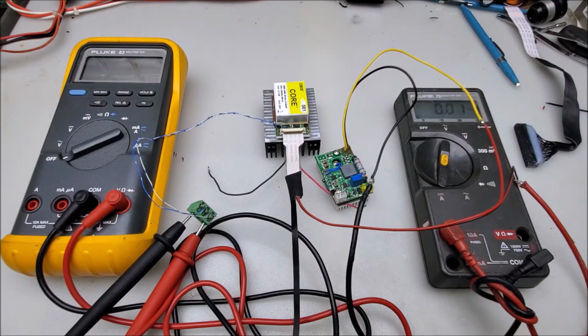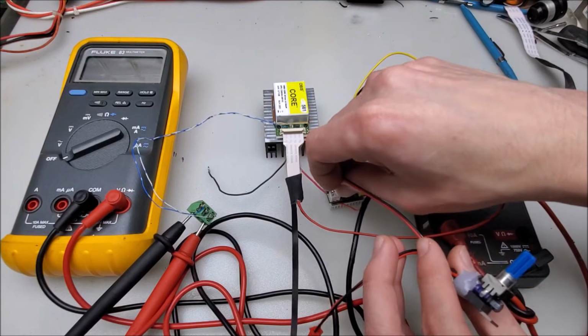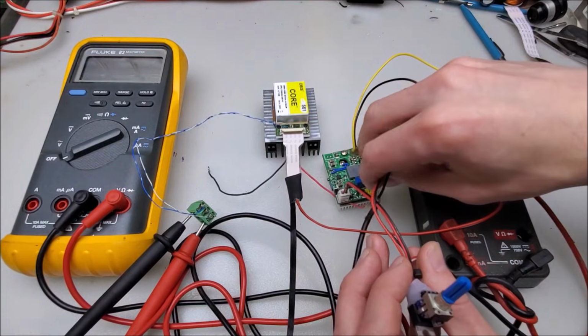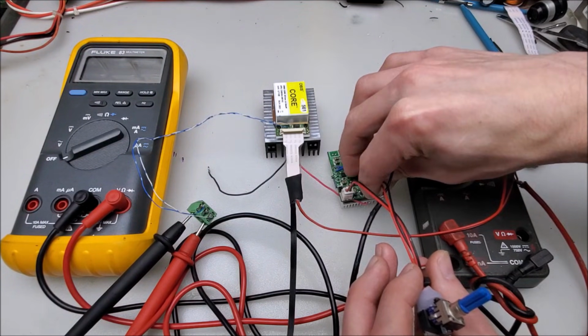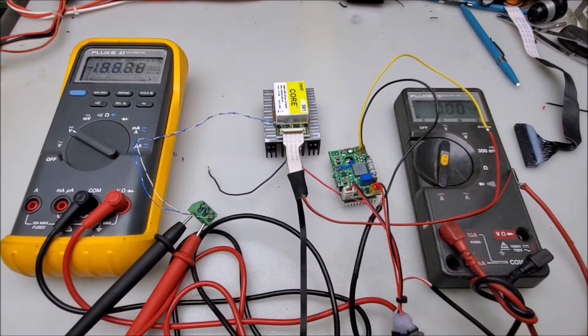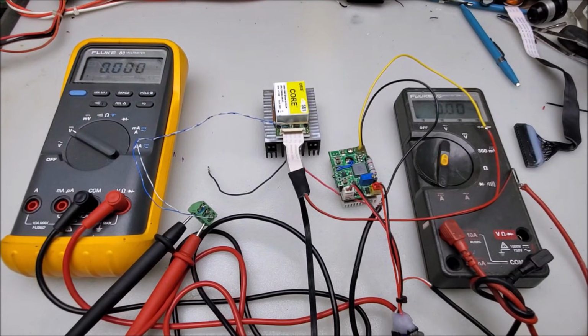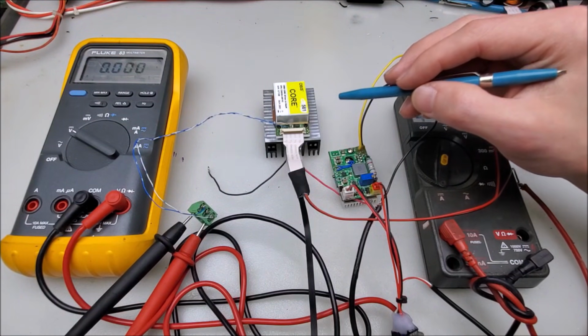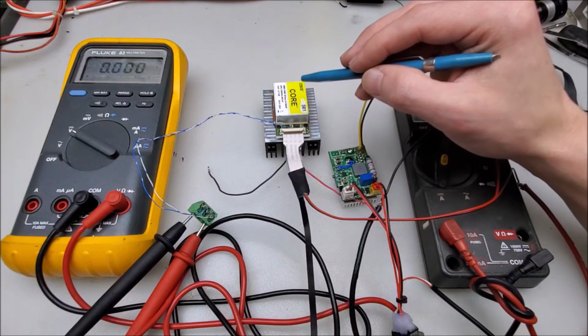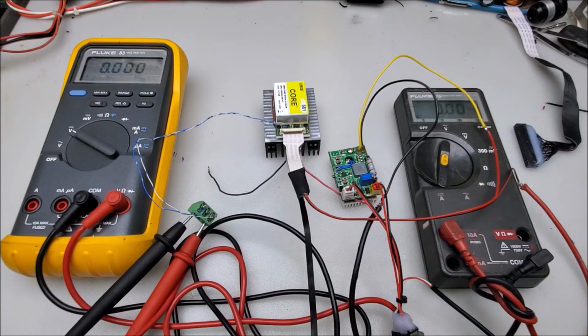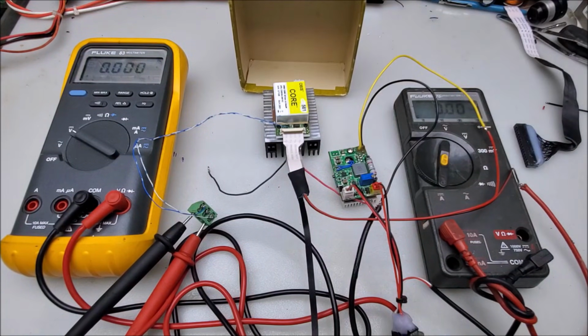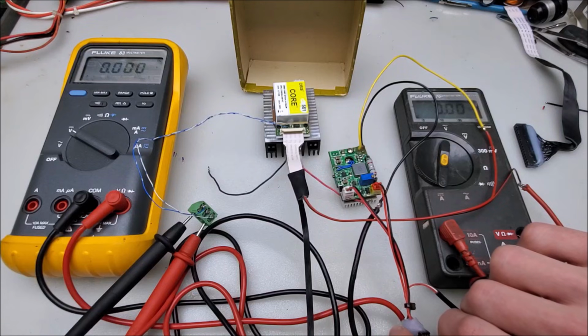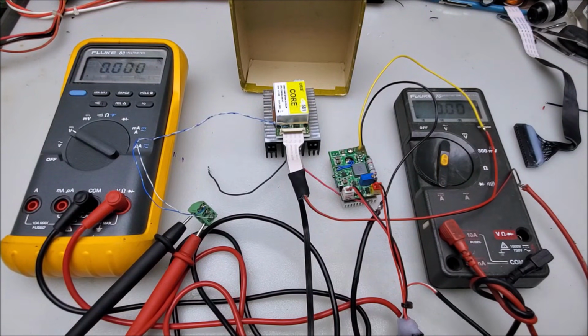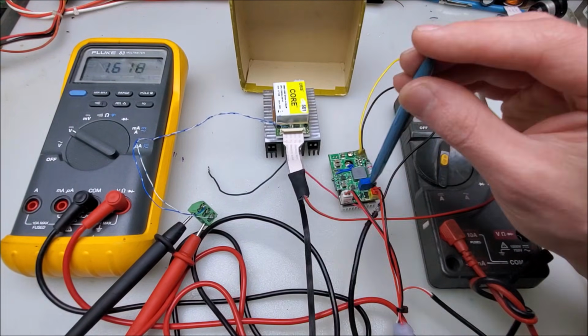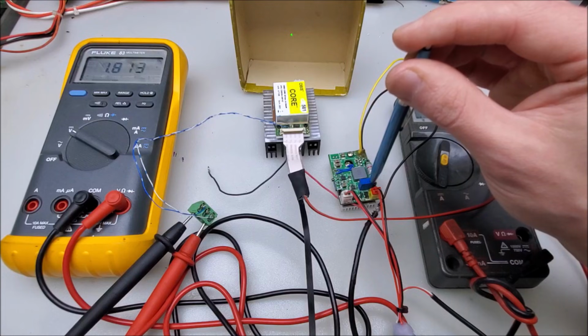Alright, we should be ready for the most part, so let's go ahead and put in power and signal modulation. That's on. Now, because the thermoelectric cooler is not running, nor are some of the heaters, yes, heaters on the inside of the laser head. Those aren't running either. We might get some output, we might not, but it won't be very efficient or very stable for long, but that's okay. Yeah, let's bring this up. Nothing, good. Let's turn up the current. See what we got. Alright, let's bring that up to like 8.5-ish.